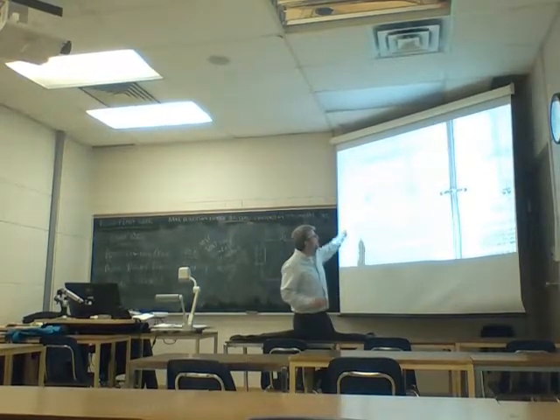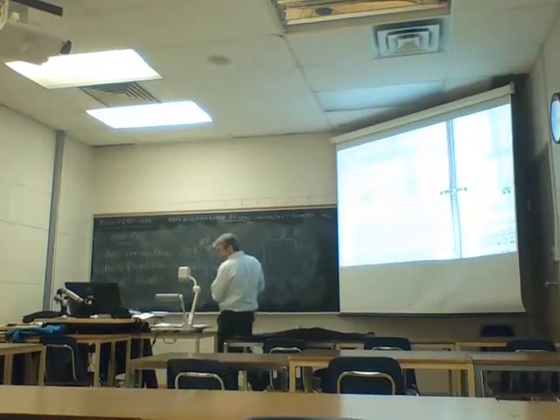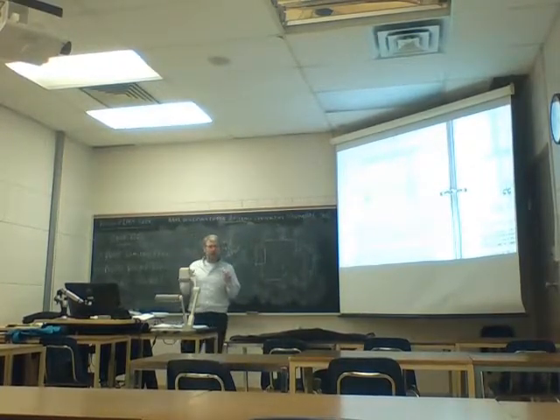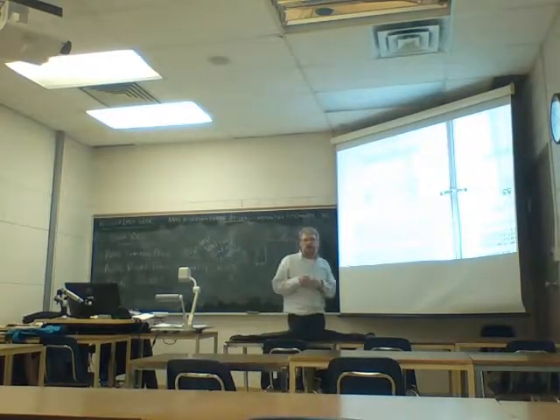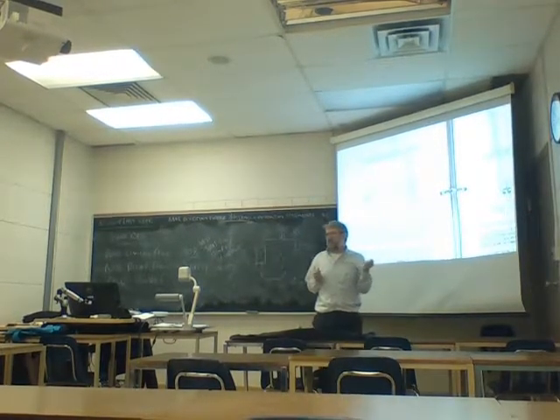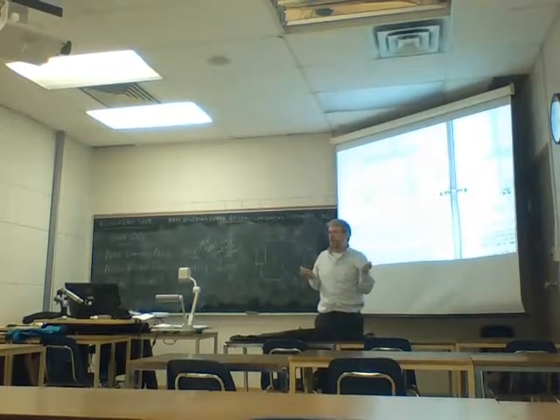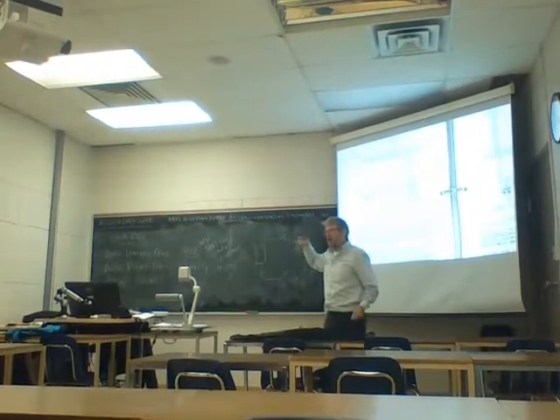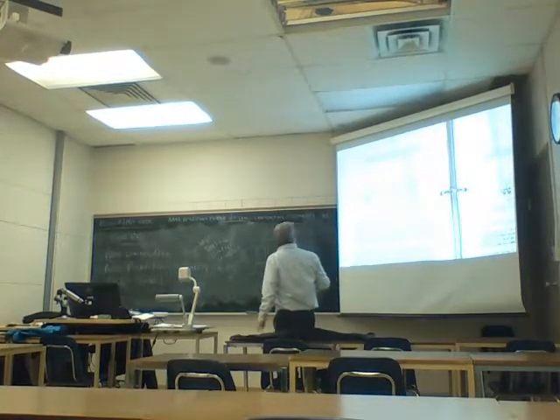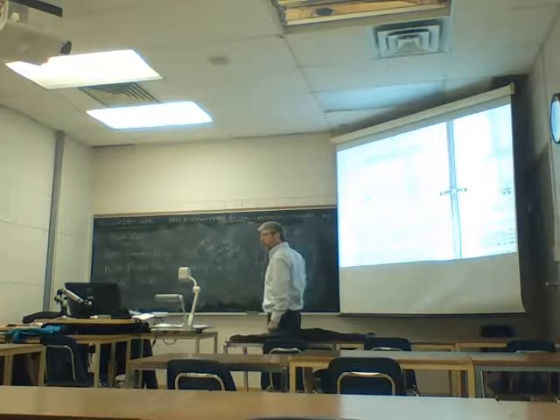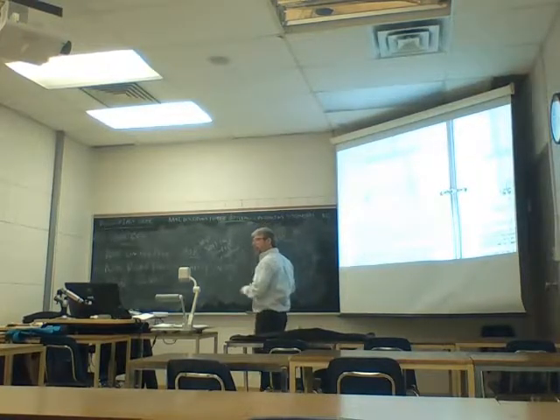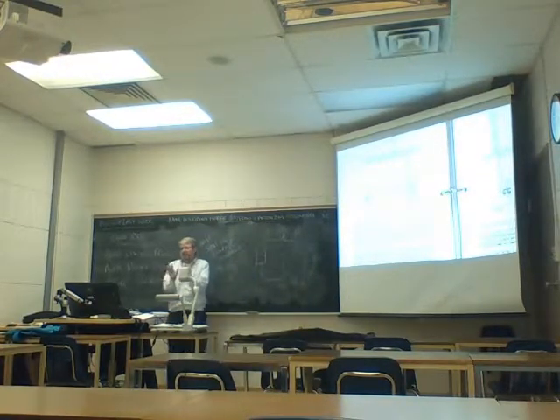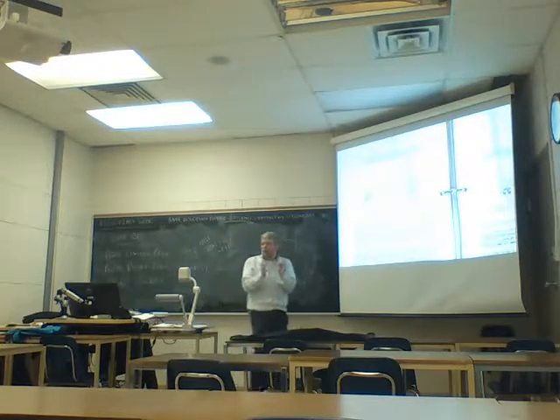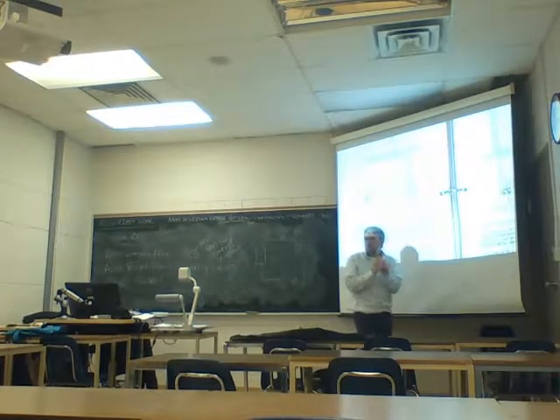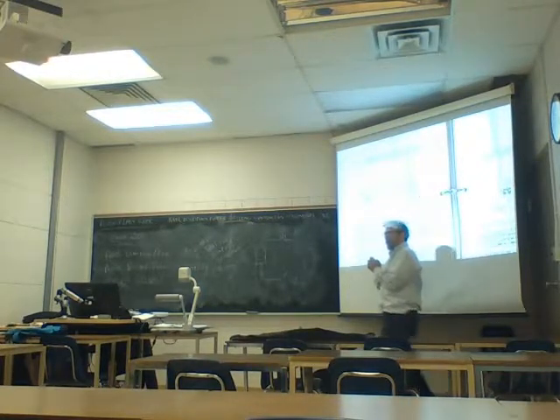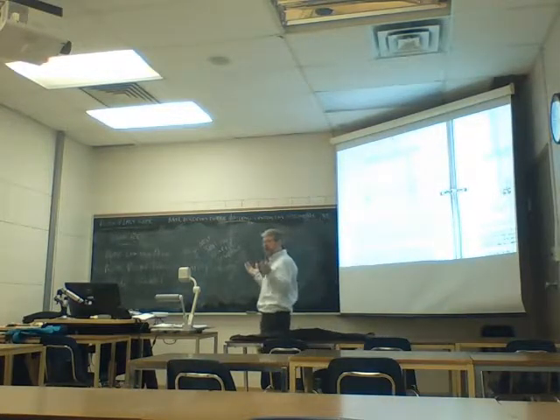So that valve can close one side. No. Why do we have dual relief valves? It's simple. It's money. They both have to be at the same set pressure. You can't have two, but you have two valves. A 6x8 safety valve is $20,000. Two 1.5x2s are $800. Same capacity. So the two valves replicate the capacity of one valve.